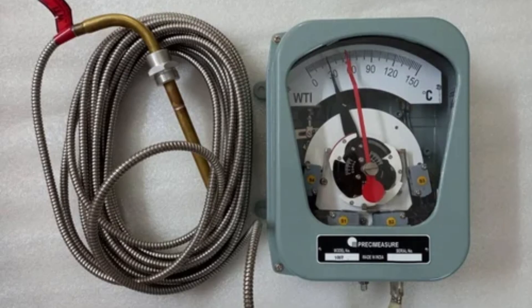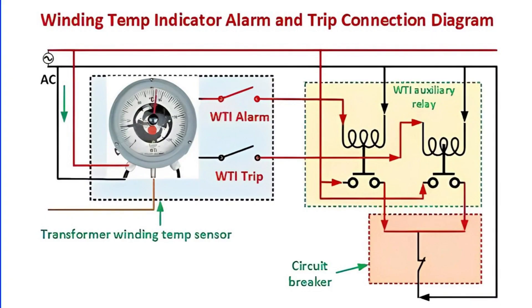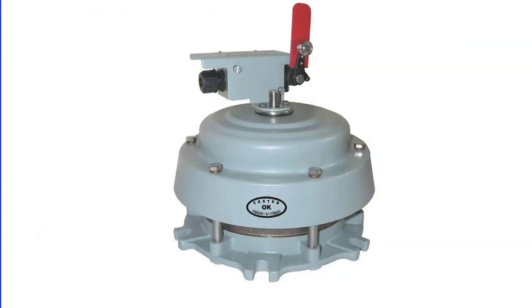Next is the winding temperature trip relay. This relay functions much like the oil temperature trip relay, but instead keeps a vigilant eye on the winding temperature. It takes action when the temperature spikes beyond a set limit, ensuring the transformer is de-energized to prevent potential damage. The pressure relief valve, installed directly on the transformer, plays a crucial role in preventing tank explosions by releasing internal pressure when it surpasses a preset limit.